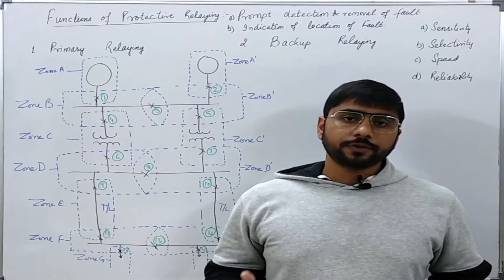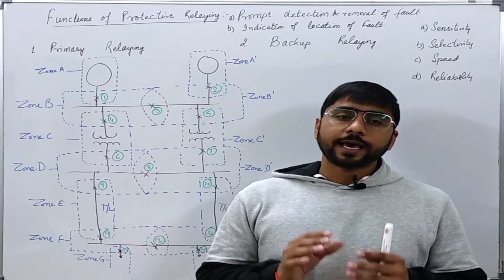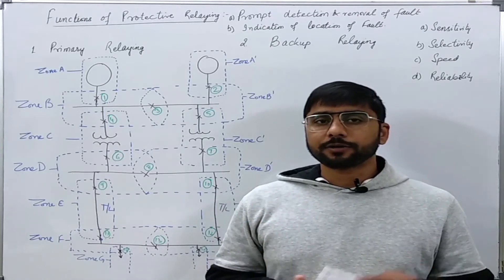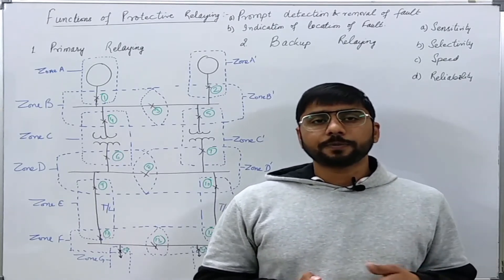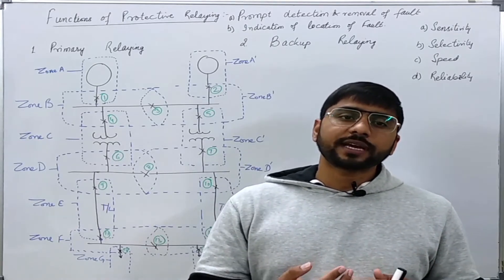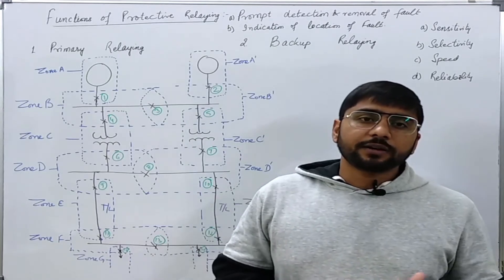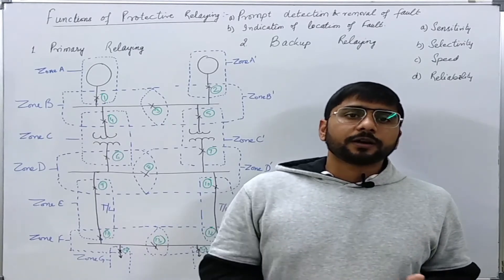The fundamental function of protective relaying is to identify and isolate as fast as possible the faulty element or faulty part of the power system. A secondary function is the approximate location of the fault so that we can easily eliminate it, attend to the faulty condition, and as soon as possible recontinue the supply.